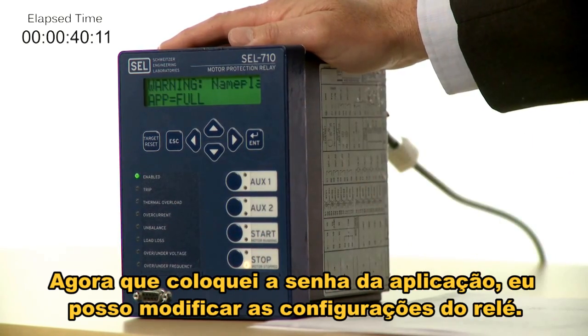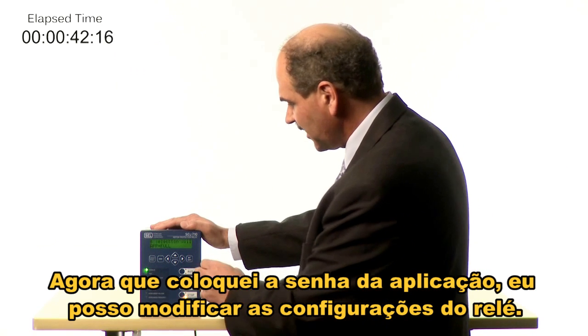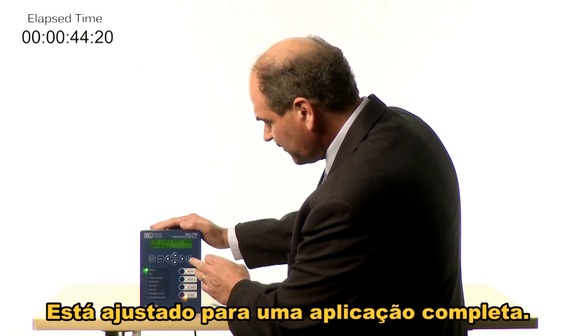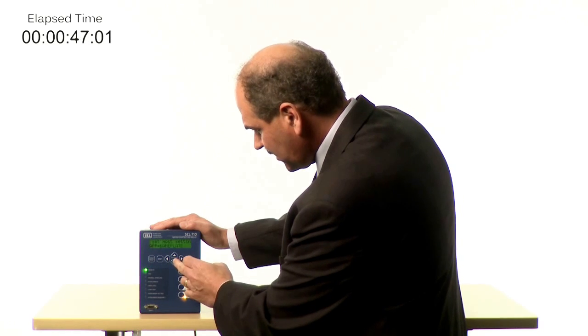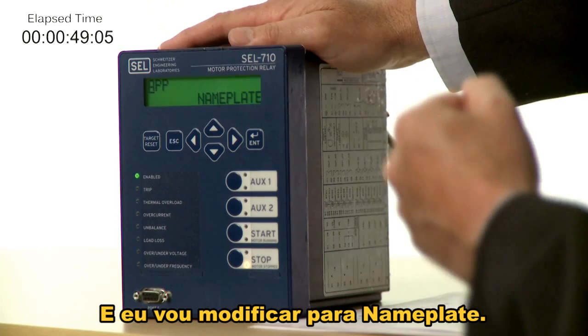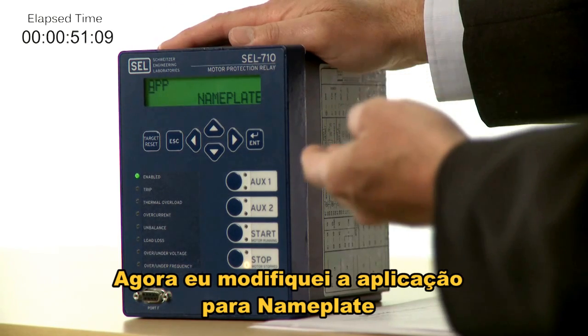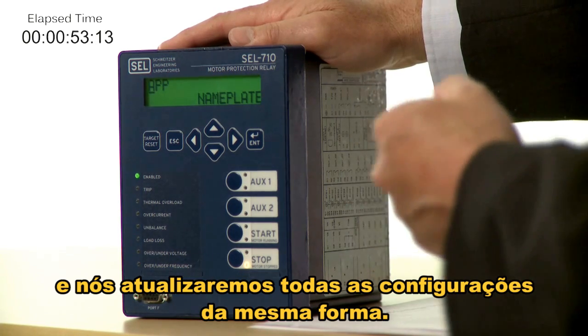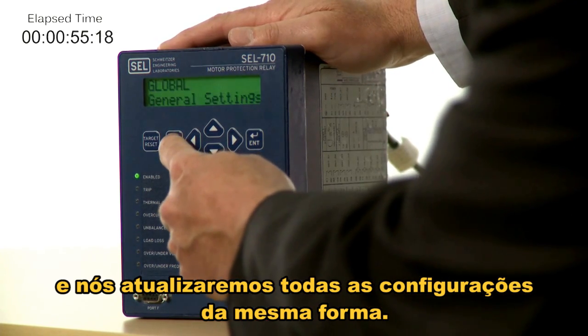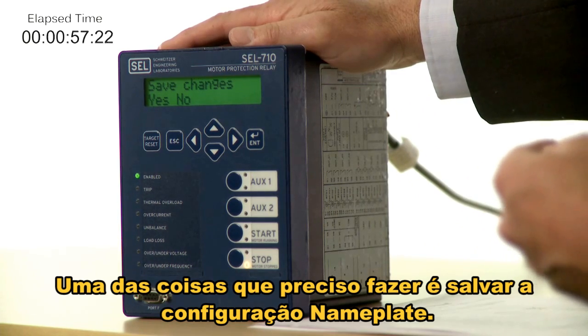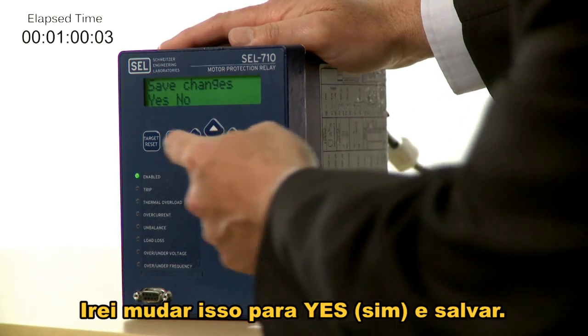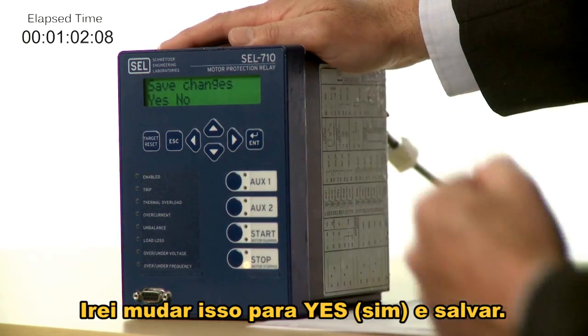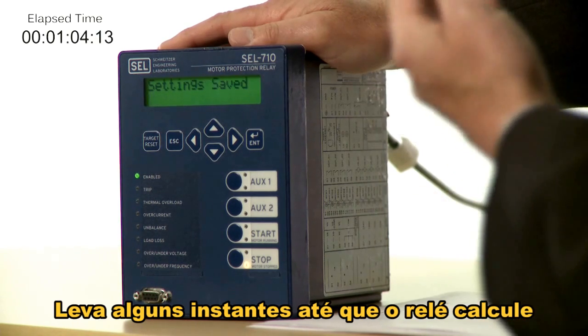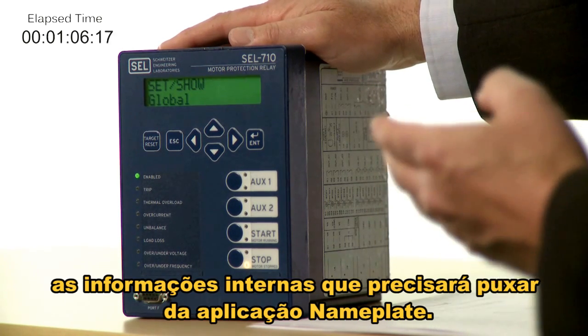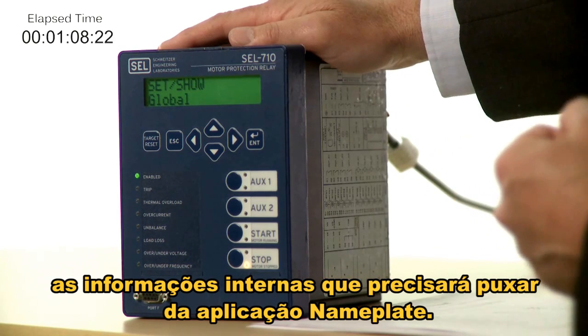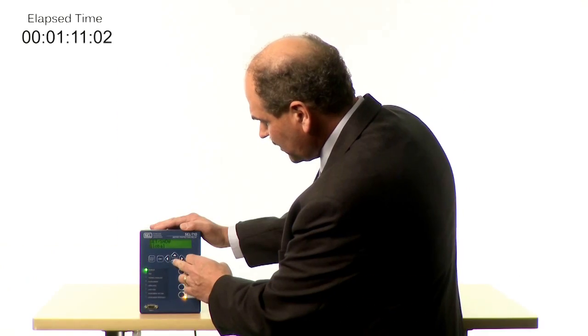Now that I've entered the application password, I can change the settings in the relay. It's currently set for a full application, and I'm going to change that to nameplate. So now I've changed the application to nameplate settings, and we'll go through and update all of the settings for our nameplate application. One of the things I need to do is save that nameplate application setting, and I'm going to change that to yes, and save that. It takes a moment for the relay to calculate all the internal settings it's going to need to pull from those nameplate application settings.